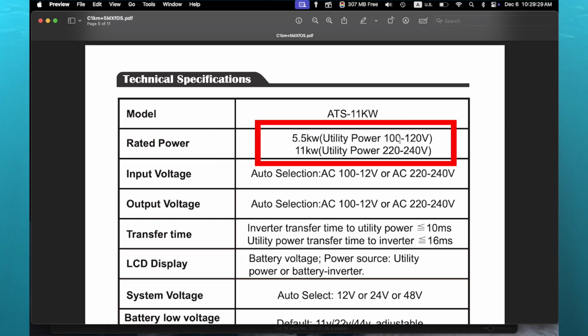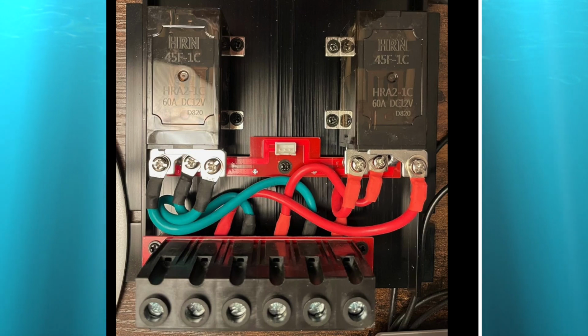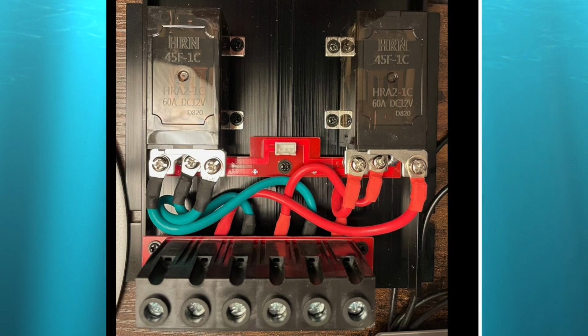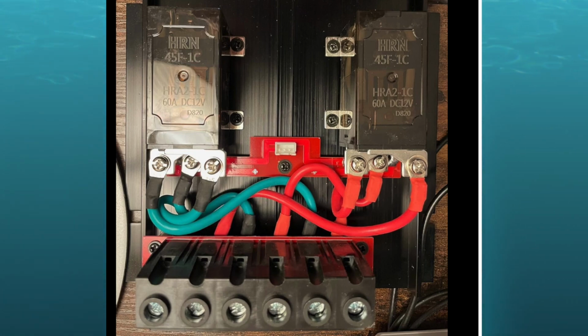The third potential problem is that the internal wires cannot handle the claimed power rating. They showed you 5.5 kilowatts at 120 volts or 11 kilowatts at 240. So the internal wires here are all like 8 gauge, which I believe would only be around 3,000 watts at 120 and 6,000 watts at 240. So you would definitely want to keep your wattage below those numbers.